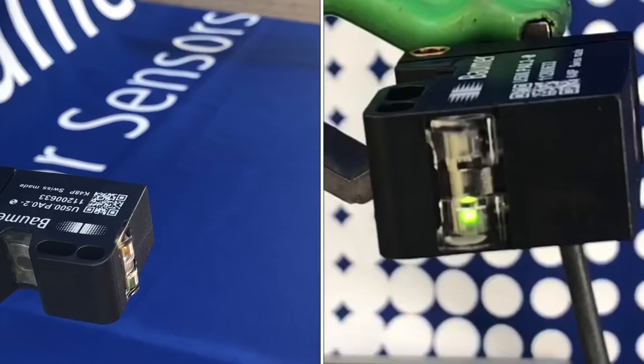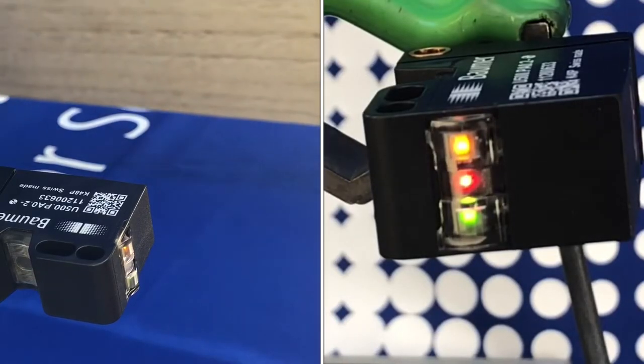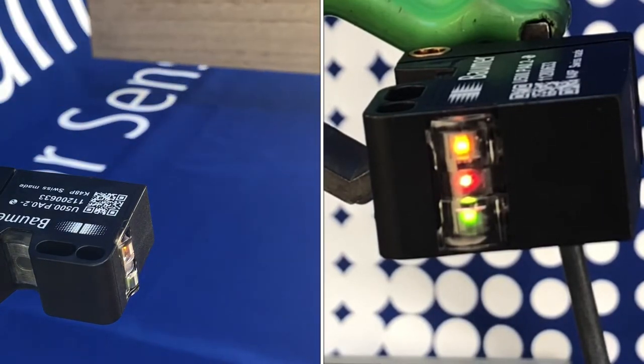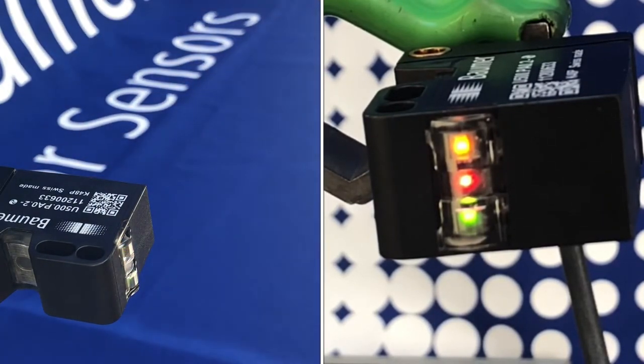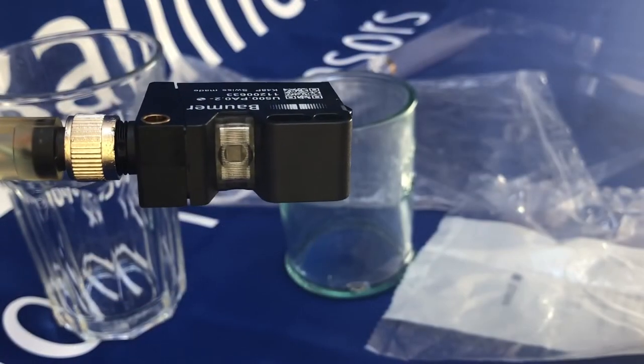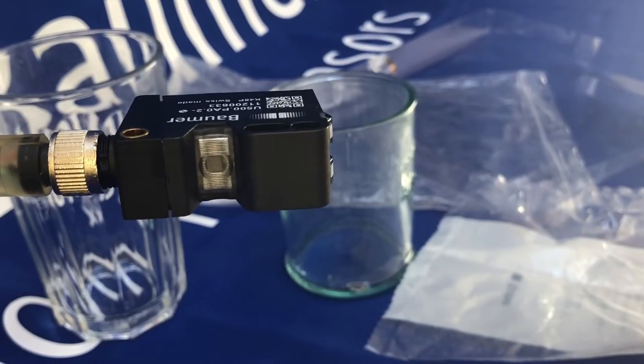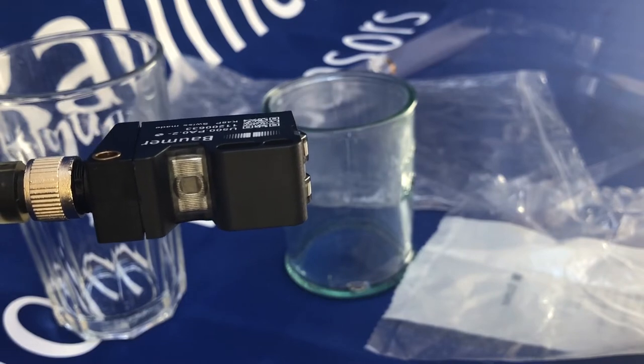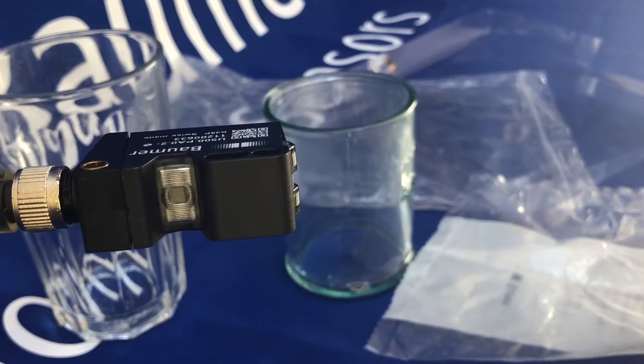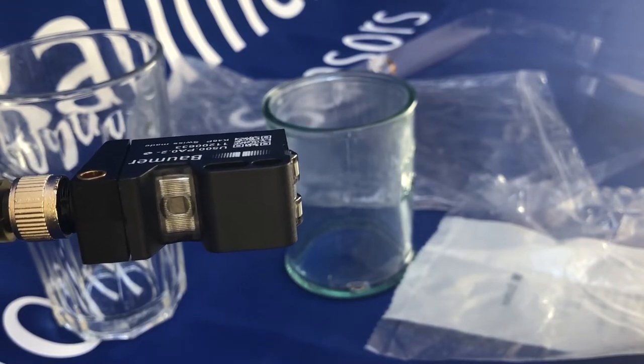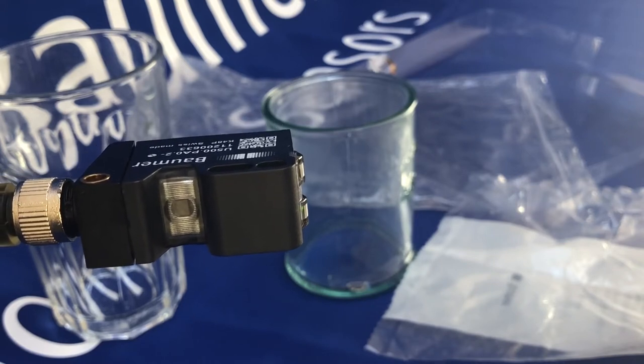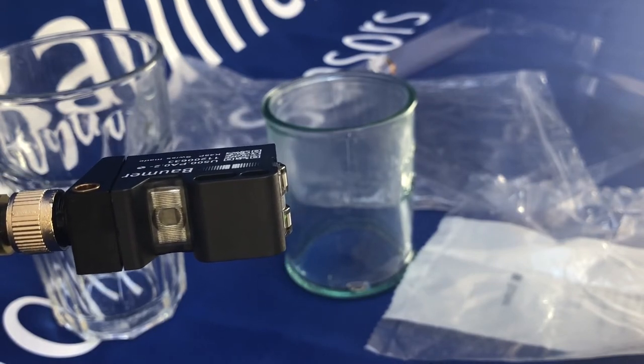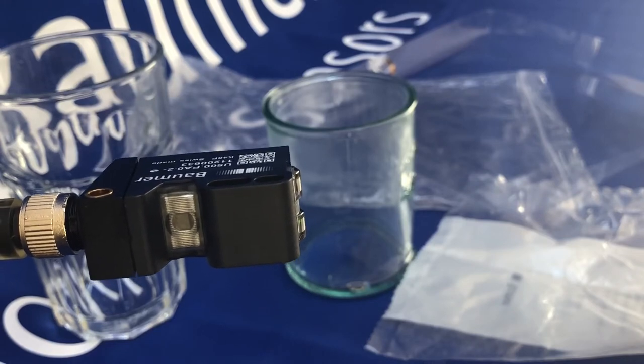This sensor has a working range of around a meter straight out of the box. You can teach the range of the U500 or UR18 sensors via the QTeach area at the back of the sensor. Out of the box, it does 20 millimeters to a meter but can be taught via the QTeach area to a specified range.